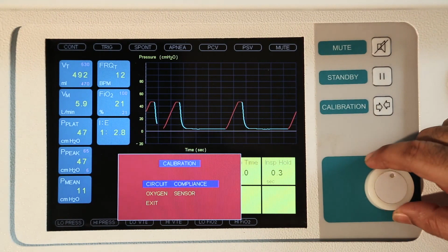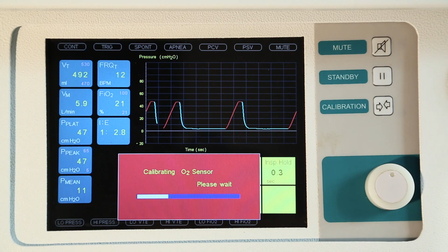To protect from that, we have an oxygen sensor which is built outside the machine and which can be interpolated between the inspiratory limb and the expiratory limb very easily. So these safety features will take our level to the next height. On top of that, we have a system where if you are using air, the nitrous oxide will be automatically locked out. So this is a very big boon for our machine, which we are standing in front of.